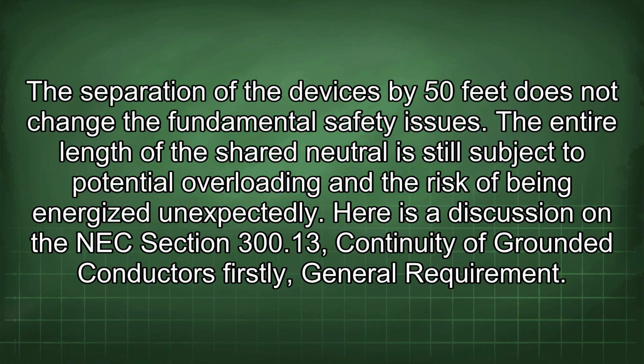The separation of the devices by 50 feet does not change the fundamental safety issues. The entire length of the shared neutral is still subject to potential overloading and the risk of being energized unexpectedly. Here is a discussion on the NEC section 300.13 continuity of grounded conductors.